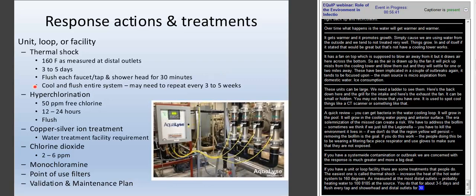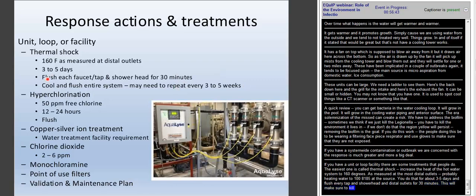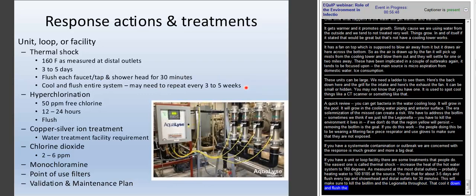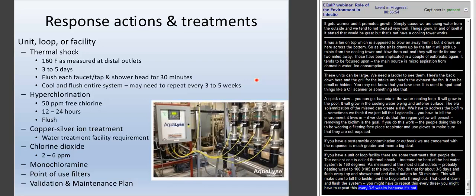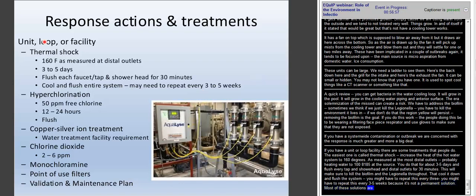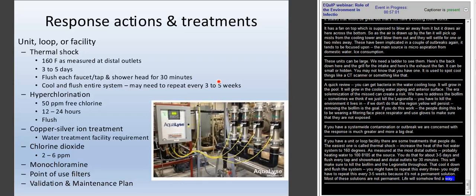Then you need to cool it down and flush the entire system. You might have to repeat this every 3 to 5 weeks because it's generally not a permanent solution. Most of these solutions may not be permanent. You're fighting a biological system, and life will somehow find a way. But this is what's used quite routinely, especially on an emergency basis, because it's perceived as the easiest and quickest thing to do.